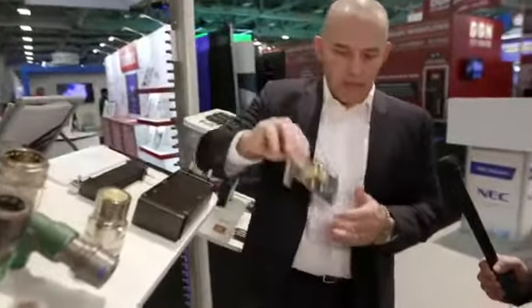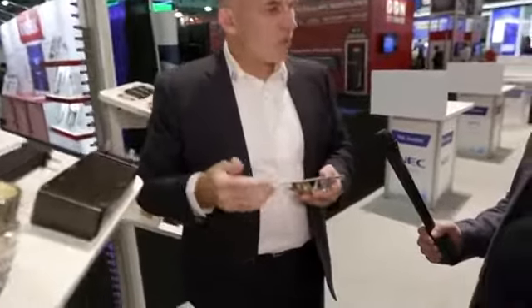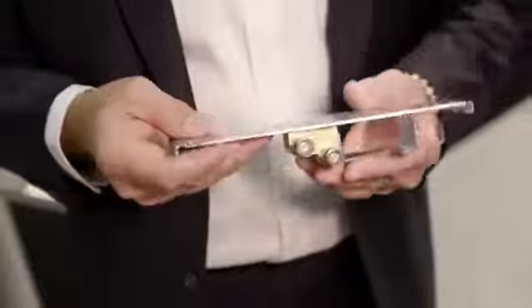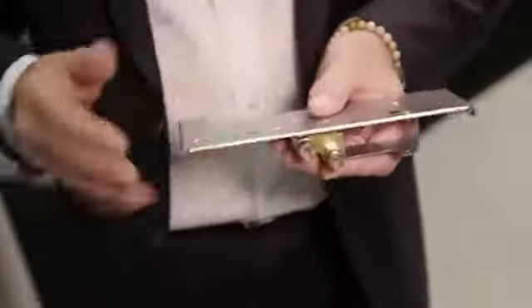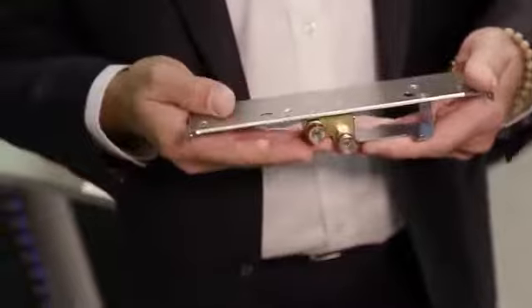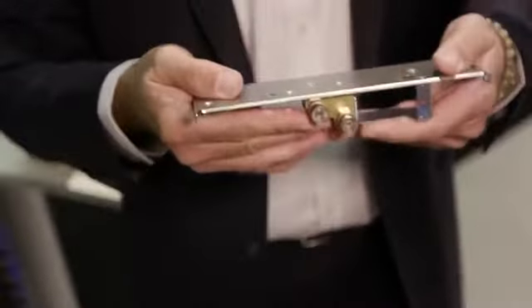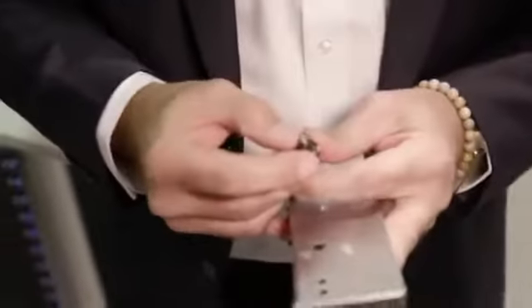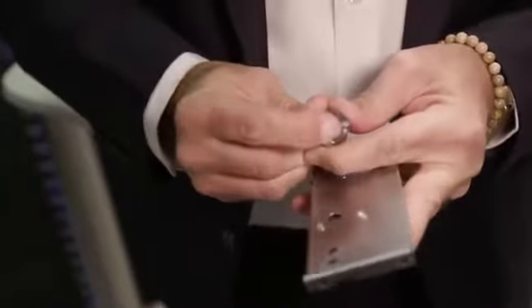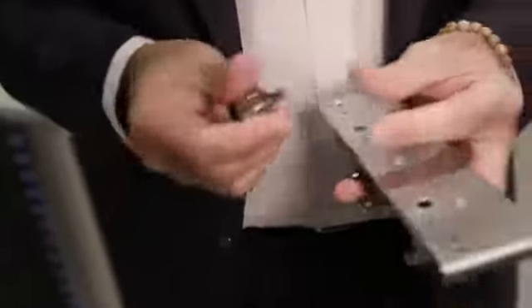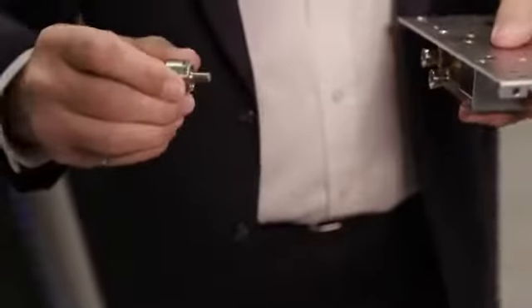We also have some specialized products here for blind mate connections. If you can picture this being mounted at the back of a server, as it slides into its mounting position, the blind connections for network, power, and now cooling happen automatically. The mating side of this connection is on a manifold, and that actually has some travel in it, so it can float and take up the mechanical tolerance necessary, so you don't have to have guide pins.